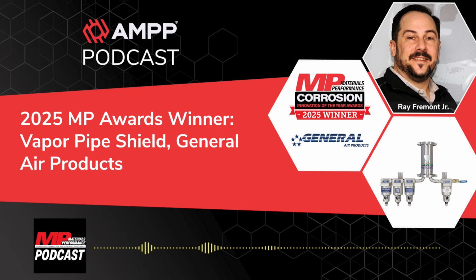It was these and more that we saw. Another big one is that the dry systems tend to have leaks, primarily caused by corrosion, but they can be caused by a million other things as well. And those leaks will grow over time, which requires more airflow out of the unit, which is not a specialty of a nitrogen generator at high purity.